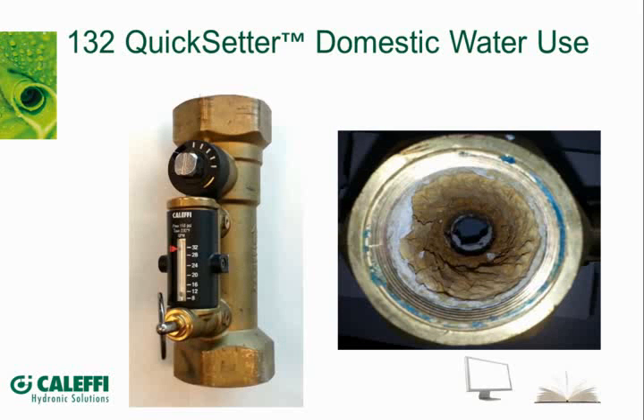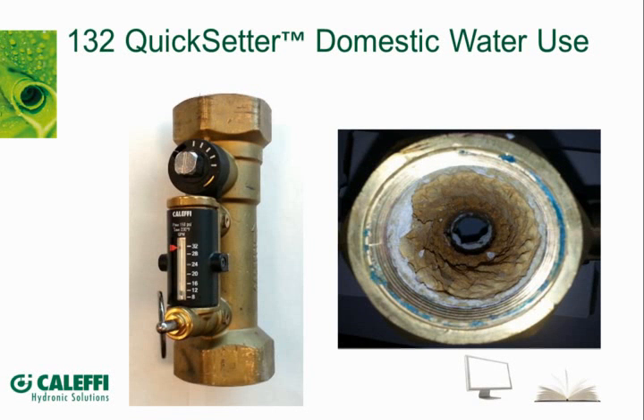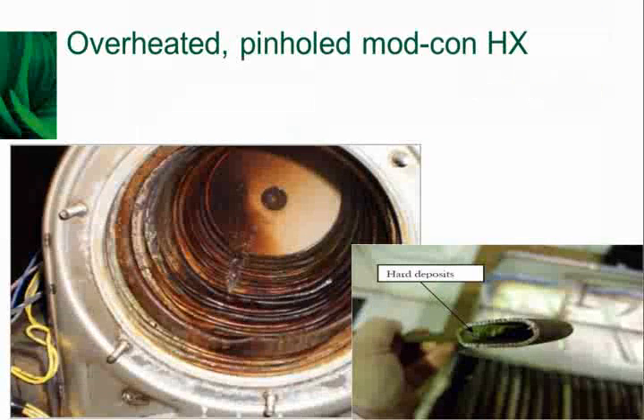Like I say, if you could open at 4 feet per second velocity, you might keep your pipe scoured, but then you could get pinhole leaks from corrosion, erosion from the fluid going around elbows and stuff too fast. Yes, you'd find those turbulence places and erosion, right. Yeah, so you're trading off one problem for another. Okay, I thought it was a good spot for that question. Yeah, thanks.